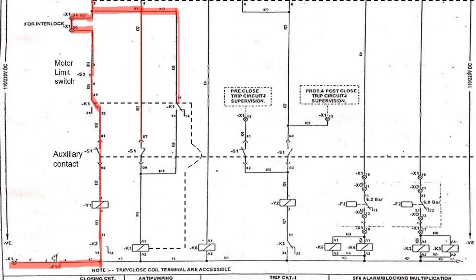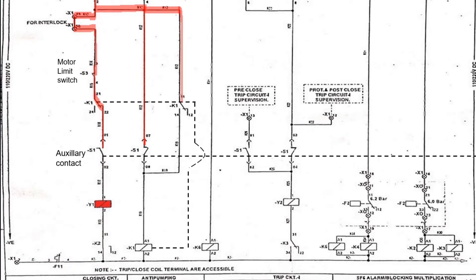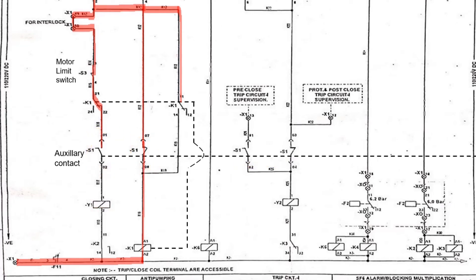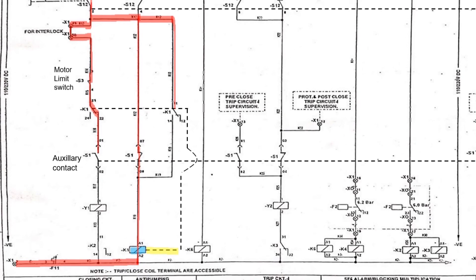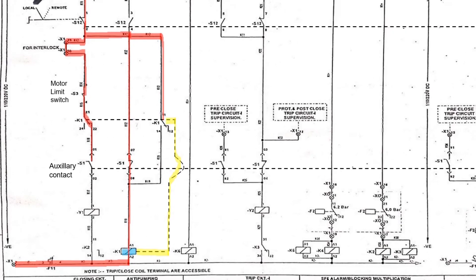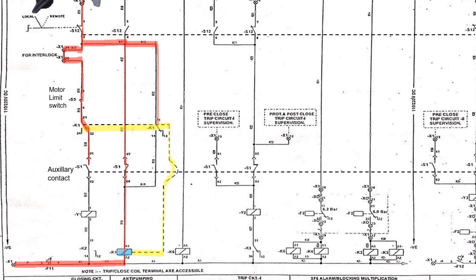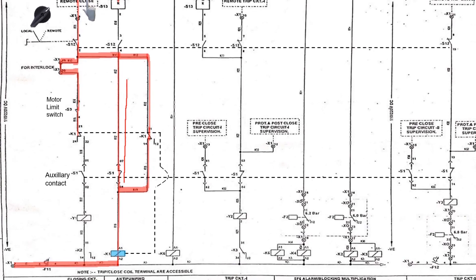Thus, energizing the closing coil Y1 and the circuit breaker closes. As soon as the circuit breaker closes, the auxiliary contacts S1 operate and change their position — all NO turns to NC and NC to NO — so the current to the closing coil gets cut and it gets de-energized. Simultaneously, the K1 anti-pumping relay is energized and the contacts of the anti-pumping relay change position — NO contact becomes NC and NC contact turns to NO — forming a closed circuit on the right-hand side and freewheeling the current after the close operation.